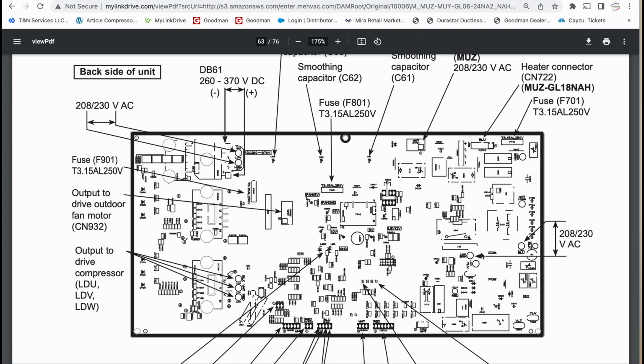Then voltage is going to feed up. It's going to feed over here to fuse. It's going to feed over to reversing valve. It's going to come through, go through the reactor. It's going to come over here. It's going to hit these 2 parts of the board right here. So if you had incoming voltage, your 208, 230, here on the right hand side of the board, but you did not have it here, at that point we would go into the wiring diagram and we could see what was going on in between.